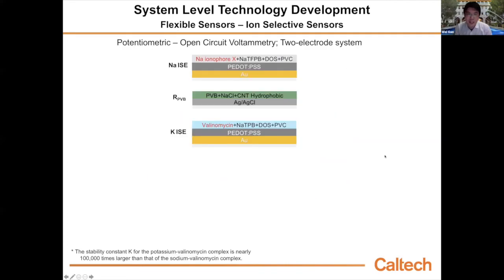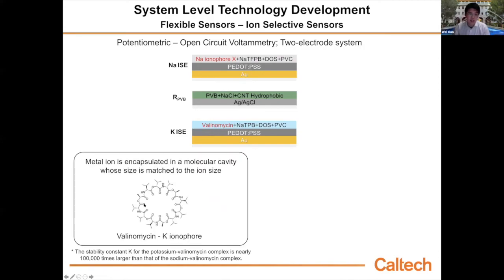To monitor ions such as sodium, potassium, hydrogen ion - basically pH - or calcium and magnesium, we could use ion selective electrodes. In this case, we immobilize our working electrode with an ion selective film. This film is selective to a given ion. For potassium ion, for example, it contains a specific ionophore, valinomycin, where the size of this ring, this molecular structure, matches the potassium ion.